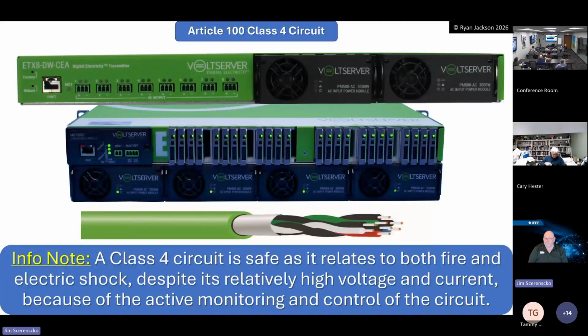There's an informational note that a Class 4 circuit is safe as it relates to both fire and electric shock, despite its relatively high voltage and current, because of the active monitoring and control of the circuit. Basically, it can't short and it can't shock because of the way it's monitored. So it's a very safe cabling system.